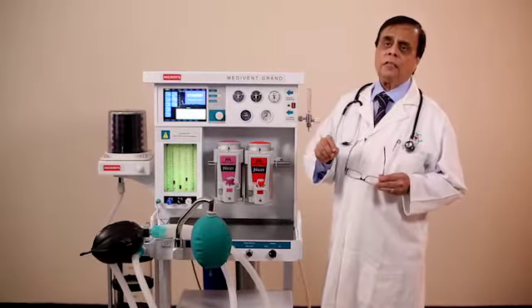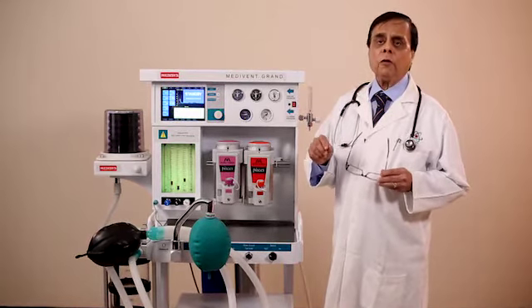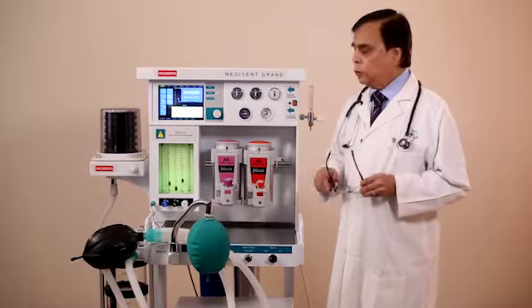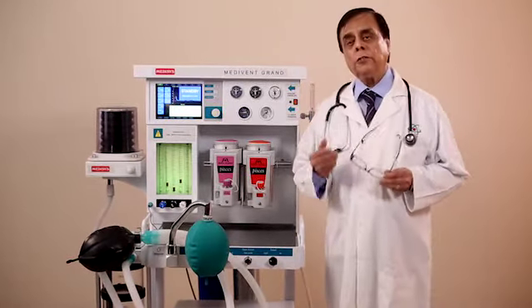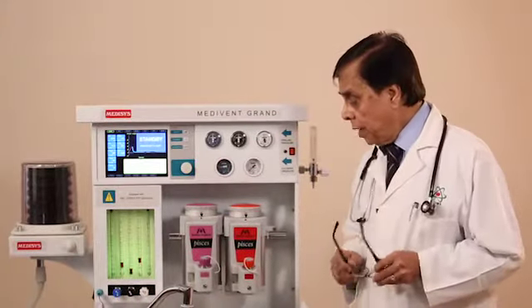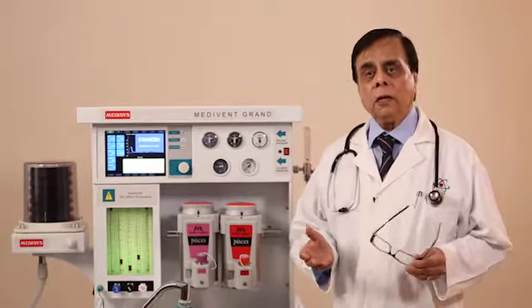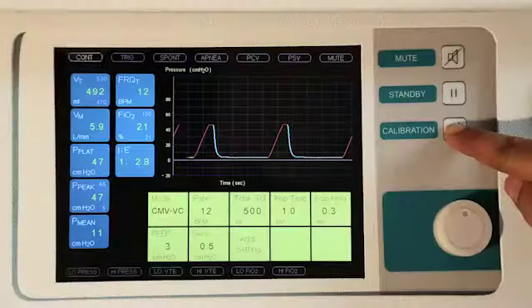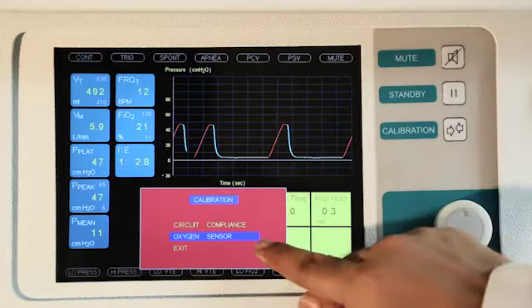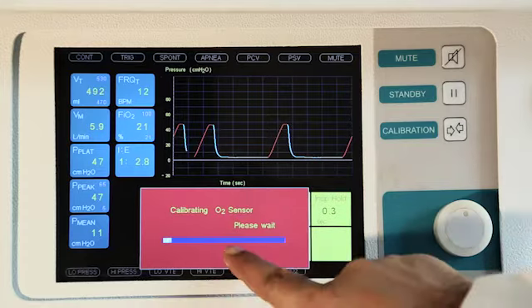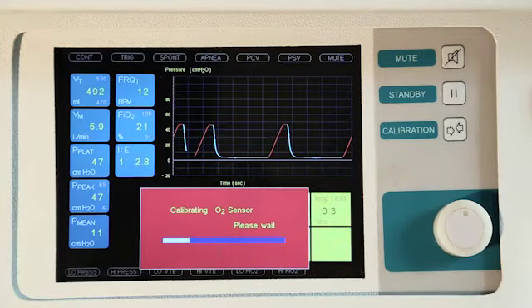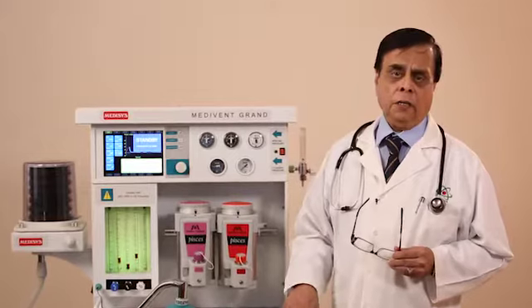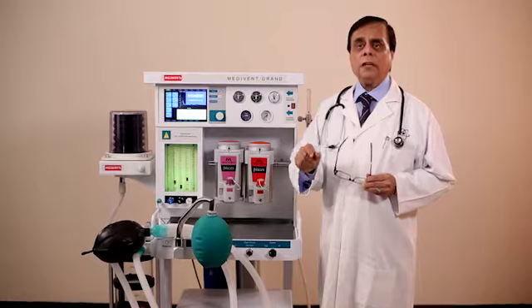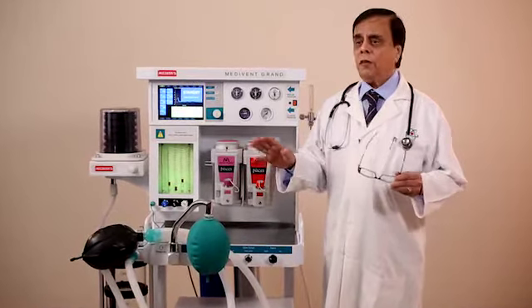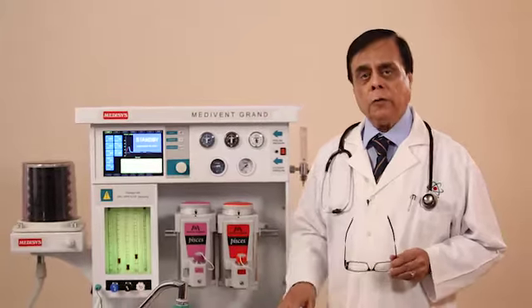The most basic danger in the machine is that it may fail to deliver oxygen at the level it is supposed to. To protect from that, we have an oxygen ratio controller. To protect from that, we have an oxygen failure device. To protect from that, we have oxygen sensors which are built outside the machine and which can be interpolated between the inspiratory limb and the expiratory limb very easily. So these safety features will take our level to the next height. On top of that, we have a system where if you are using air, the nitrous oxide will be automatically locked out. This is a very big boon for our machine.